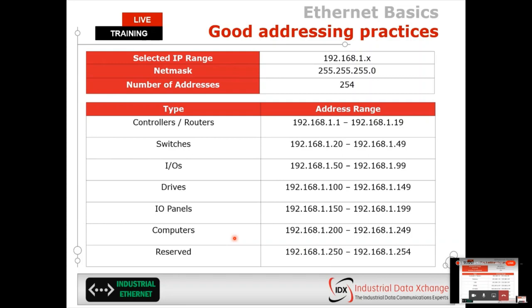This has actually been quite a challenge. A lot of the time I'll do site audits and call outs on industrial Ethernet networks, whether it's Ethernet IP or PROFINET. When you get to the site, because of poorly documented available addresses in the network, a lot of the time I can't assign a free address to my diagnostic tools on my laptop. That's a challenge, because if I accidentally assign my laptop to an address that's already in use on the network and plug it in, it's likely I'm going to cause a network failure or trip on that network. So it's important to keep that documented and available, with a procedure for assigning those addresses.